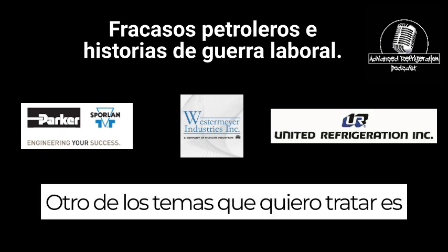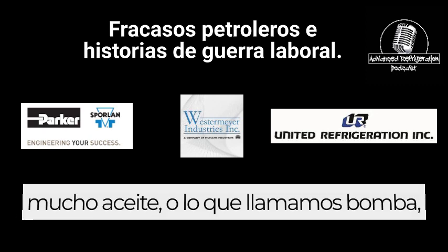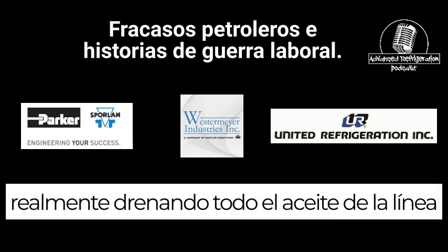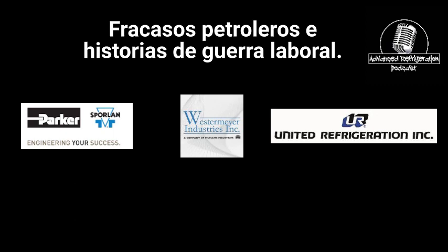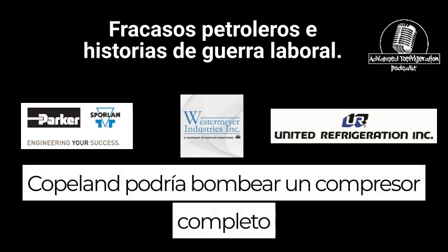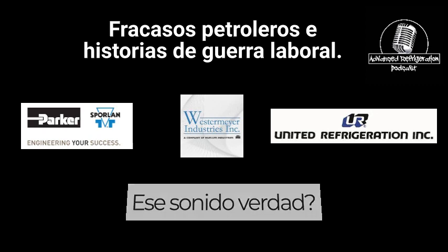One of the other issues I want to cover is when you have a compressor that's sucking out so much oil, what we refer to as a pumper. Basically one that's sucking out so much oil that it's draining all the oil out of the line as well as the oil reservoir. Typically, a 4D Copeland might pump out a whole compressor in probably an hour and a half, right? Does that sound right?